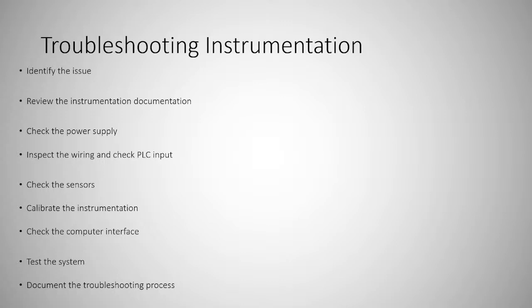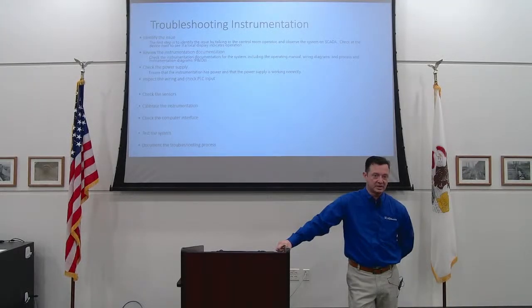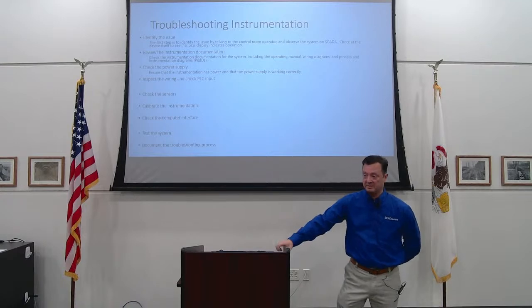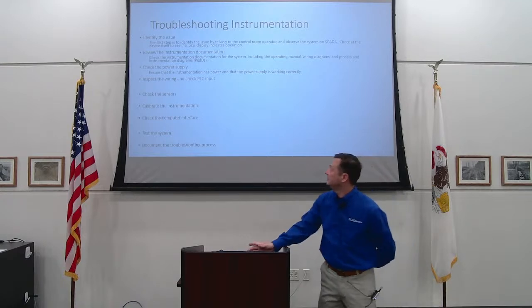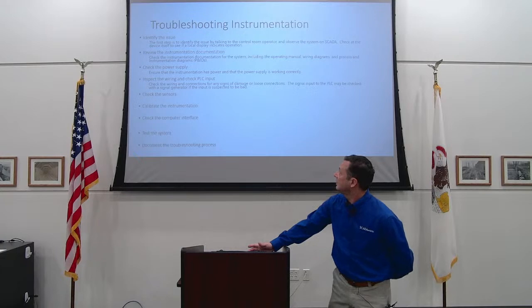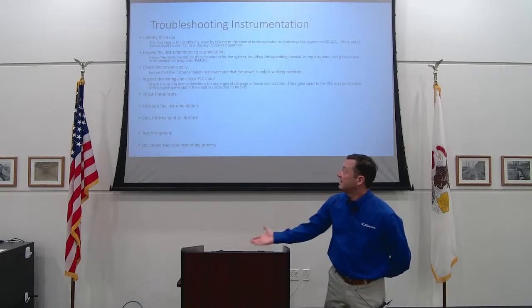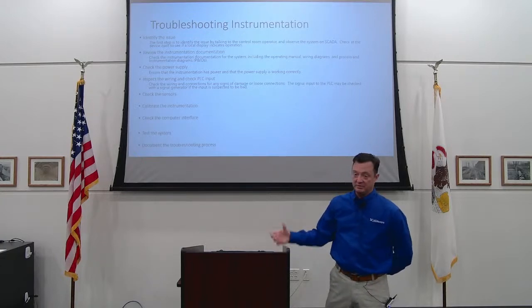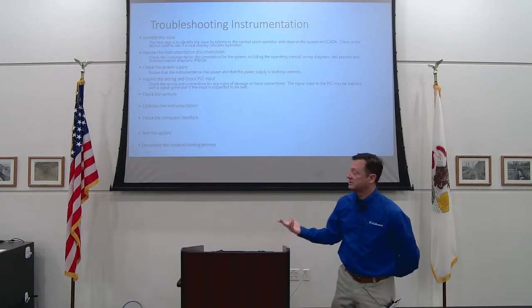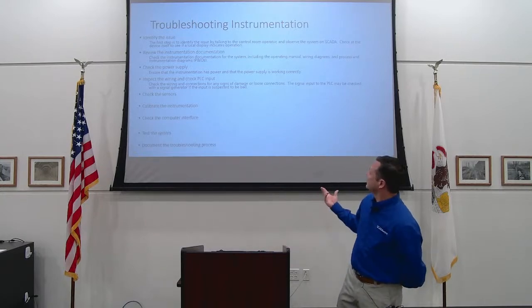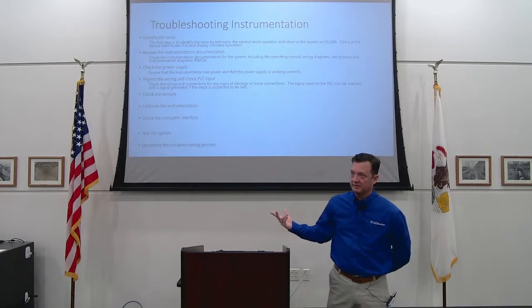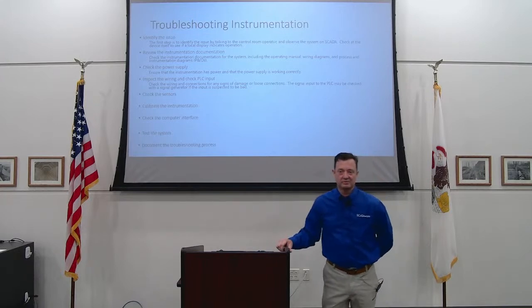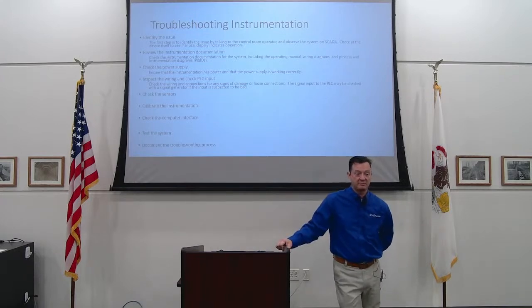The most likely cause of a lot of instrumentation problems is power, right? So you lose a power supply, or maybe a fuse blows or something. Check power that you've got to the instrument. Then inspect the wiring and check the PLC input. Make sure that there are no loose connections. The PLC input signal will normally be checked by an integrator, I would think, but it's something that I've been able to talk operators through in the past over the phone.